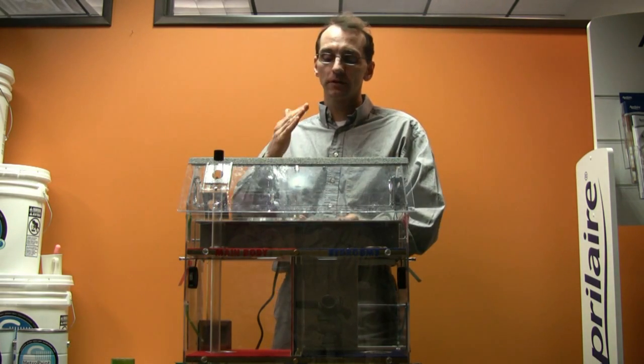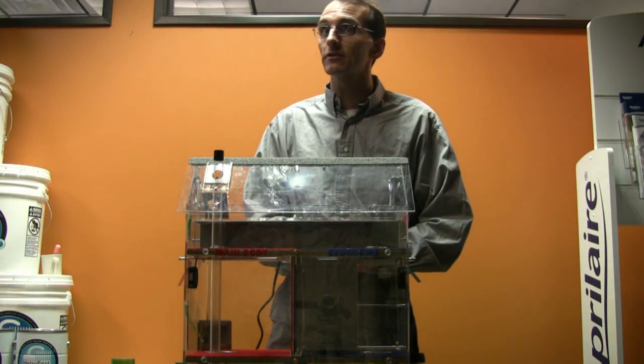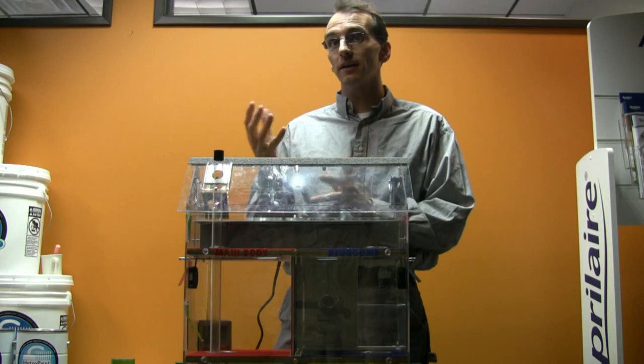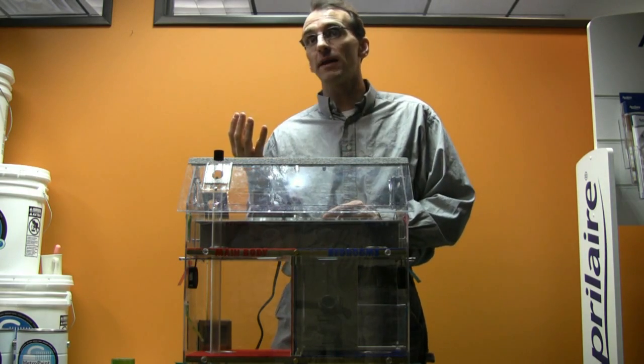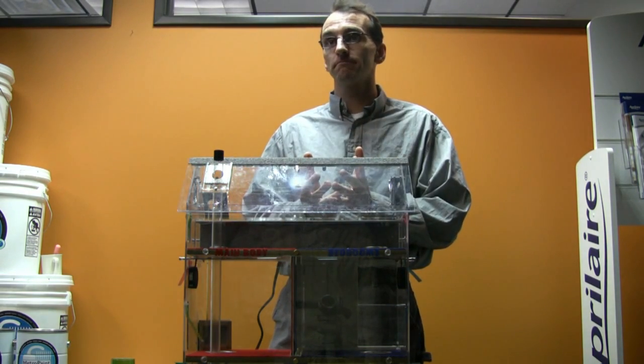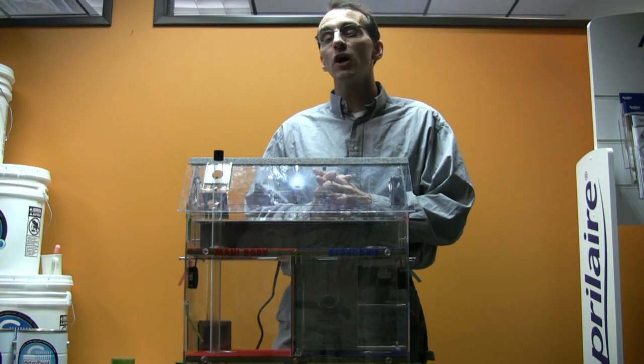If you're building a new home to some green building certification or even just Energy Star certification standard, you actually need to mastic using a water-based paste. You need to mastic all your seams. So you put the mastic on the joist first, and then you would install the sheet metal to the bottom of the joist?